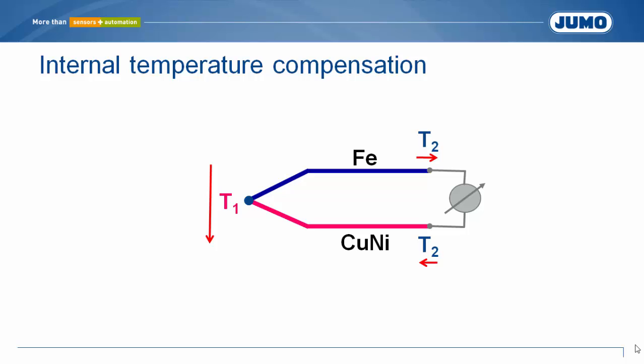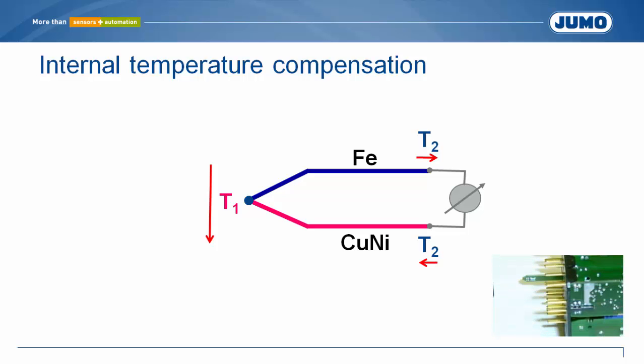In JUMO field devices, therefore, an RTD temperature probe is located close to the terminal. The RTD temperature probe measures the terminal temperature T2. T2 is added to the measured value T1 minus T2. This process is called internal temperature compensation and is used to determine the measuring temperature T1.